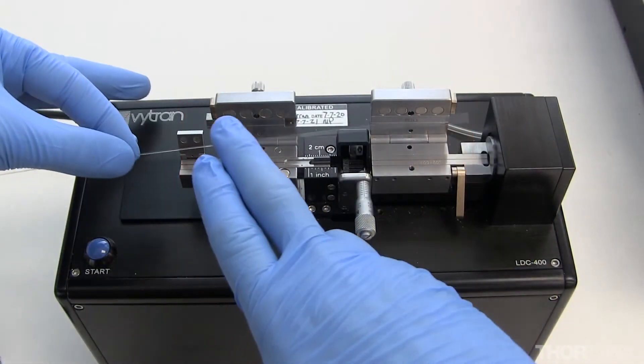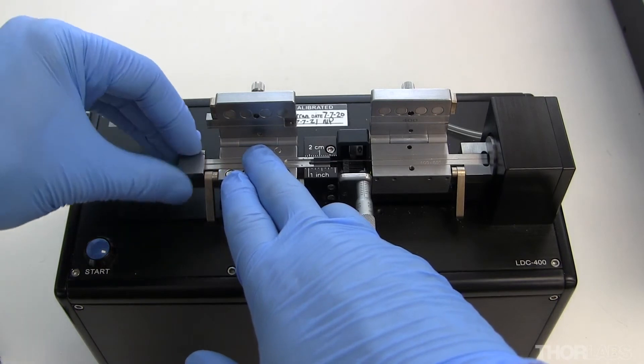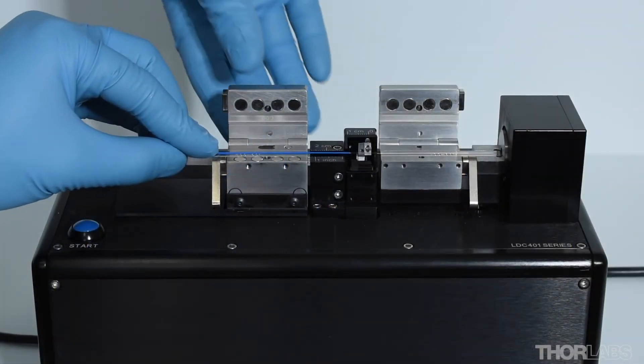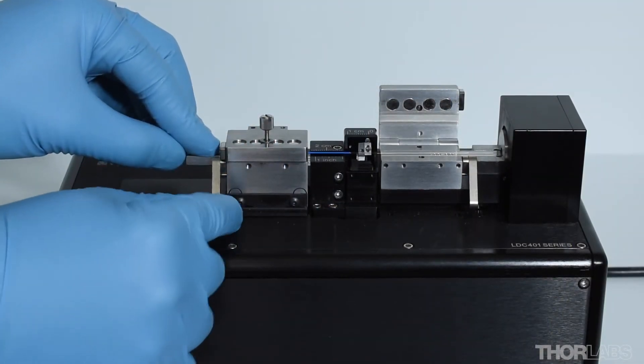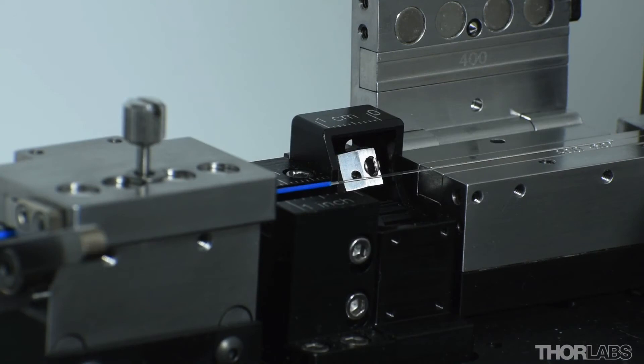Now secure the reference fiber in the left fiber holding block using either a transfer insert or by closing the left fiber holding block lid. Do not clamp the reference fiber in the right fiber holding block. This will prevent damage to the blade when it is moved to the service position.